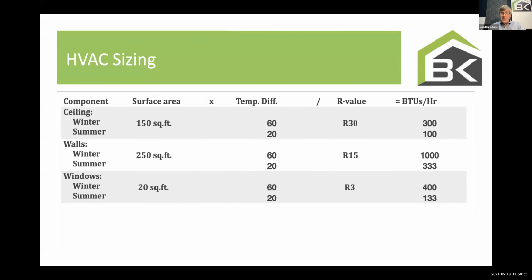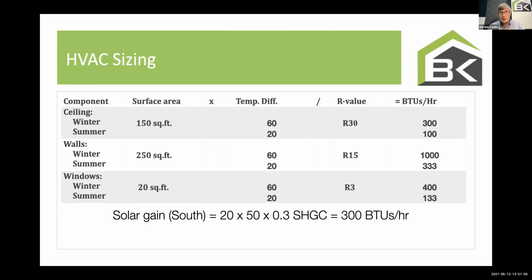So that's just the conductive gains and losses through the window. Now, if you apply the solar incidence, if I said this window was on the south side, I would have 20 square feet times, remember the 50 BTUs, times 0.3. I got 300 BTUs. Wow. In terms of heat gain, only the walls are bigger than that window. That one small window facing south is almost as much heat gain as all of the walls in that room. So the windows are a big deal.